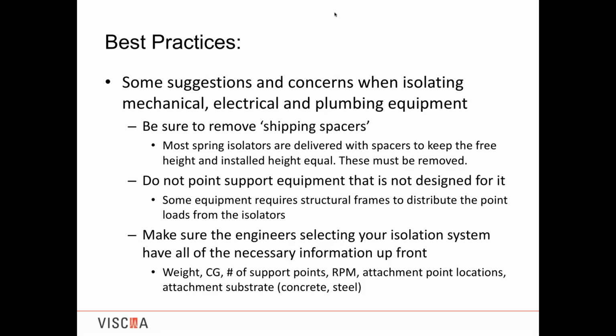As you're adjusting one corner of a piece of equipment, you're transferring weight back to the other corner. So if you've removed those spacers, you're going to bottom out the opposite corner of the equipment. It's no different if anybody's familiar with cars and watching NASCAR and they're turning screws on one corner of the car, they're moving weight to another corner. It's very similar on a piece of equipment adjusting isolators. So you need to keep the shipping spacers in there until you can remove them all, and then you'll level out the equipment and you won't short circuit.